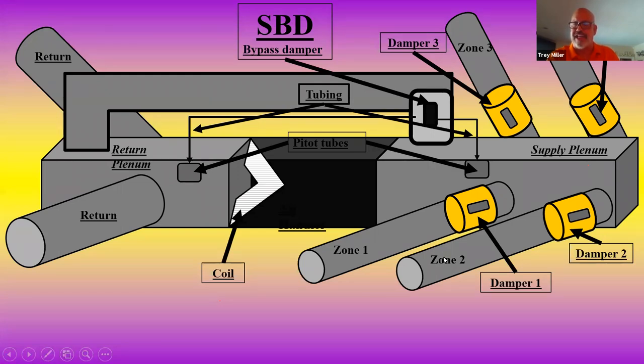Make sure you get into high fan speed. Once you're in high fan speed, let it run for 3 to 5 minutes. Make sure our ductwork is pressurized. Gentlemen, all you have to do is push the flashing yellow light. The light will flash yellow to let you know that we're ready for setup. Once you push the light, the damper will close. Take an external static pressure reading across the system. Then it will open. Take another external static pressure across the system. It goes through its algorithm, gentlemen.